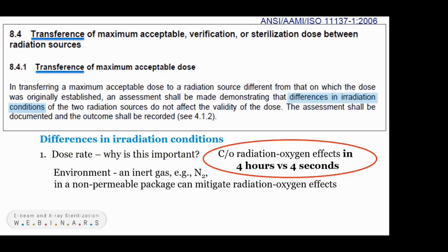So that's critical. The note here is that you can mitigate that. We used to do that at the University of Maryland, where I studied in the lab for radiation and polymer science, and we'd put samples in an inert environment, sealed in a pouch not permeable to gases. Gases couldn't permeate, and that would compensate for this oxygen effect, so you'd get the exact same results in e-beam, even in sensitive materials, between e-beam and gamma. So you can mitigate that through inert environments, but that has to be considered and assessed.